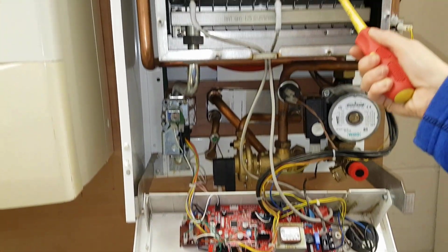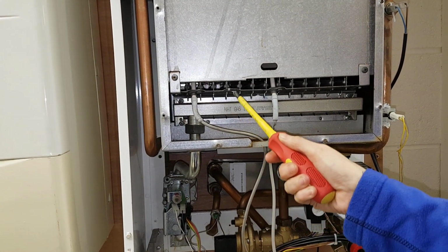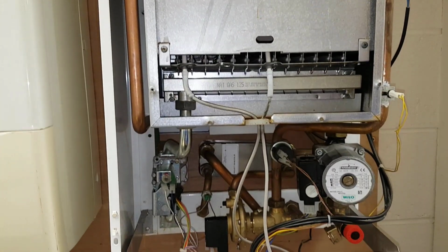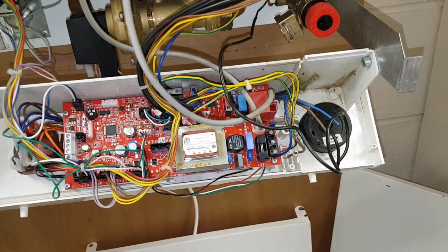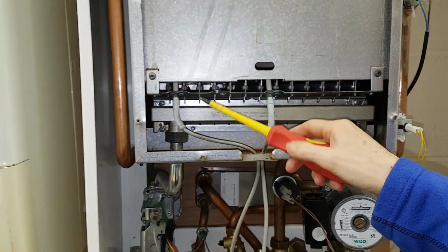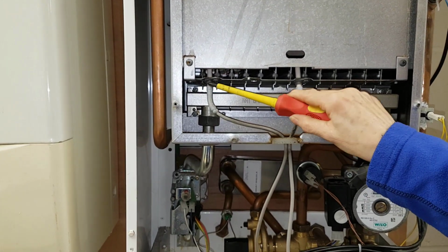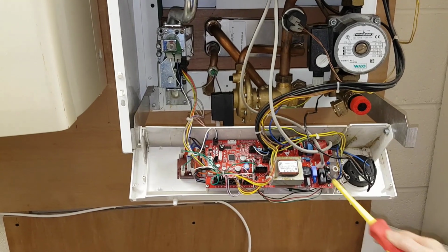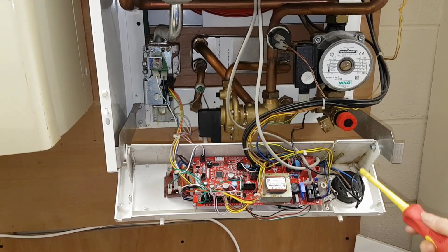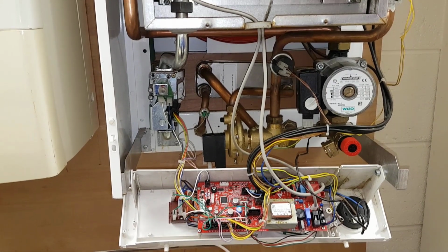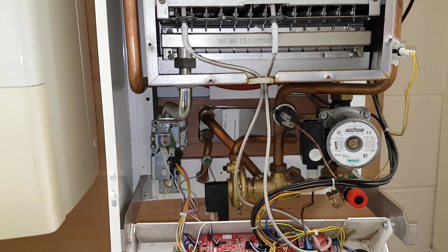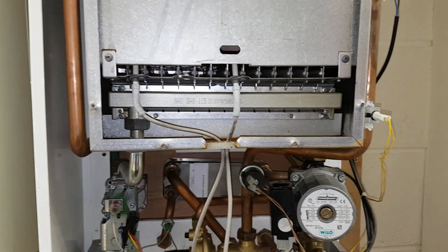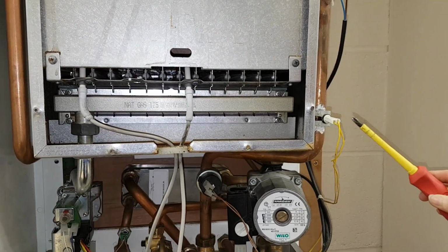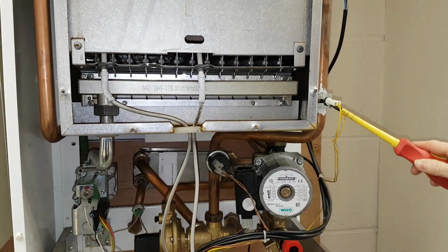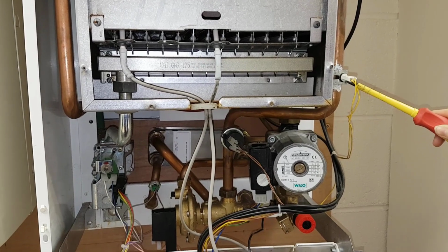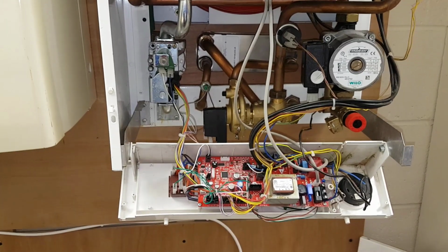Gas is then into the burner and mixed, and then ignition happens from the board. That's a spark generator, and it's ignited. It's picked up by the flame sensing electrode, which goes back to the board, and that completes the ignition cycle. If that is complete, then the boiler will start to run and circulate and provide heat to the radiators. Then it's sensed by the temperature, by this primary sensor here. If this is faulty, it can stop the boiler running. Excellent. What do you think, guys?